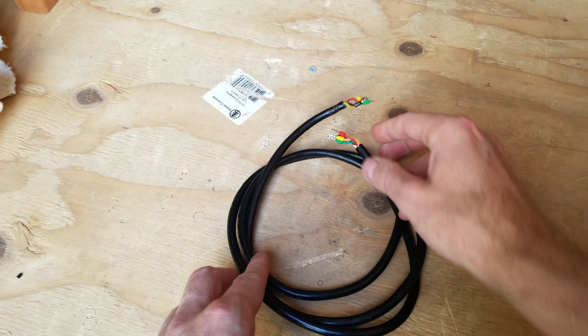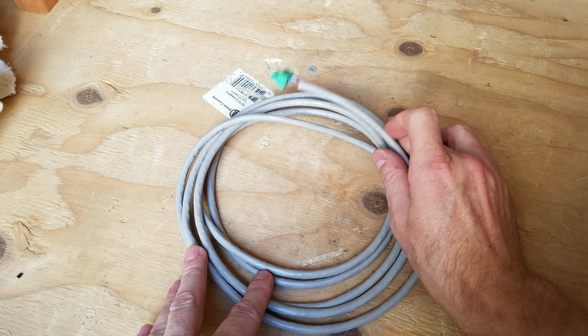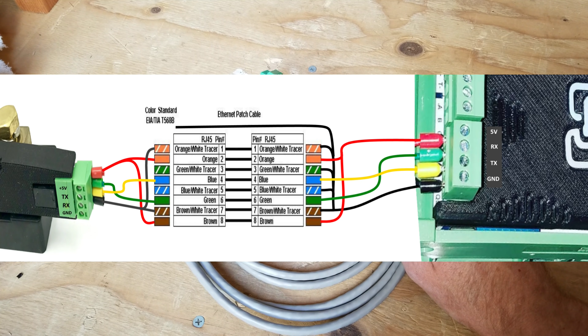This is the cable that comes with the Batrium shunt, and since my Batrium is mounted on the other side of the container from my electrical panel with the shunt in it, this cable is too short. I talked with Batrium about this, and they recommended using standard Ethernet cable for lengthening your shunt cable if needed. They provided this diagram as a good basis for any serial connection, with maximum noise suppression. Once you get into that, it goes beyond my level of understanding.